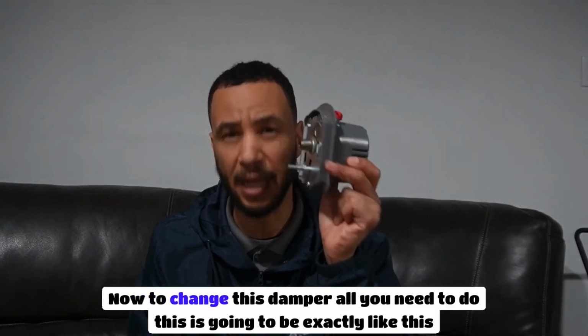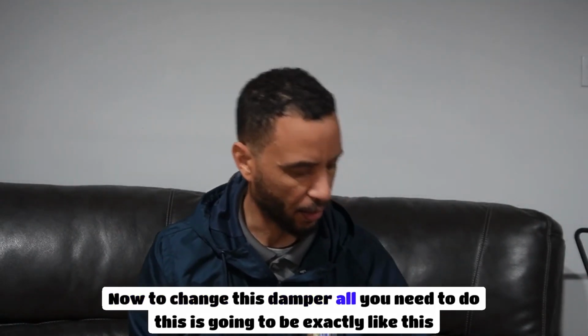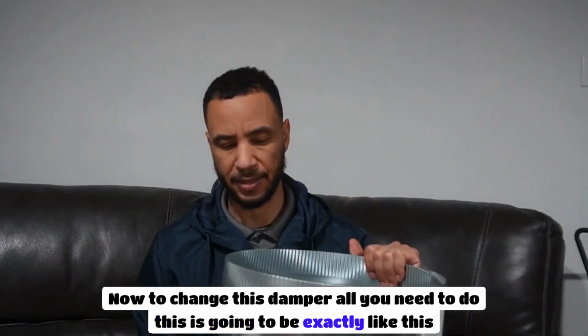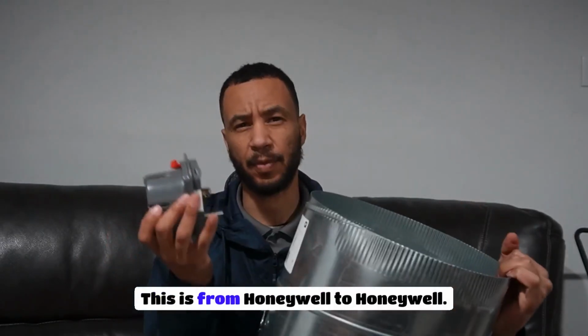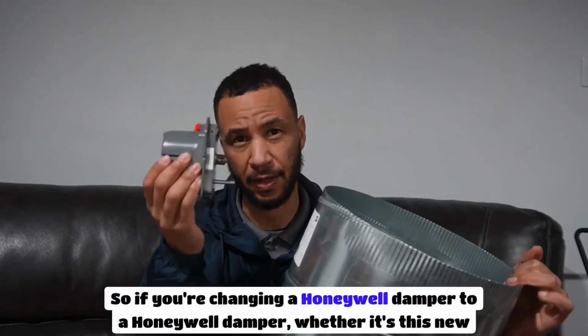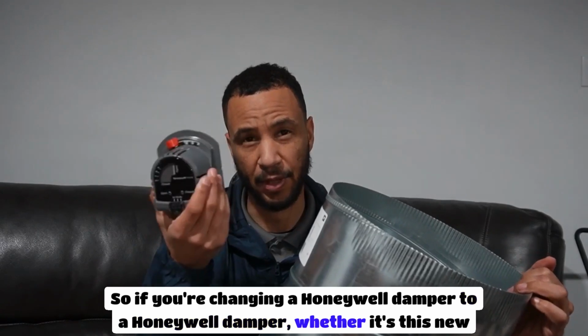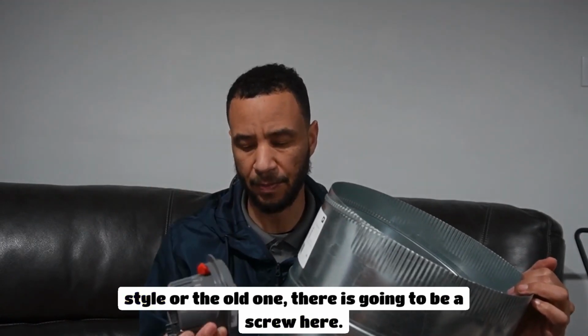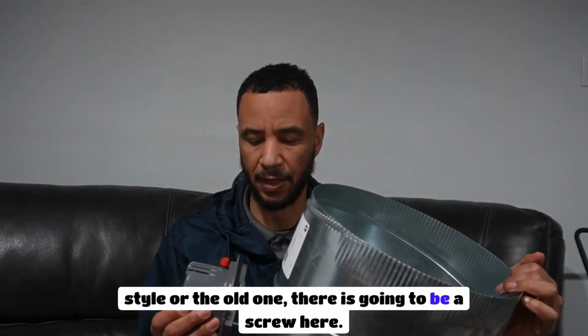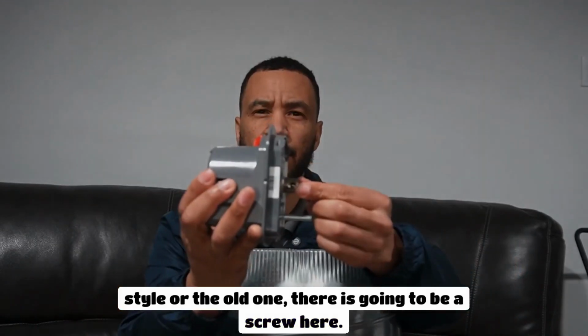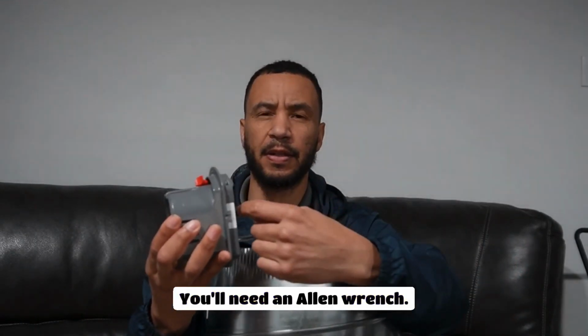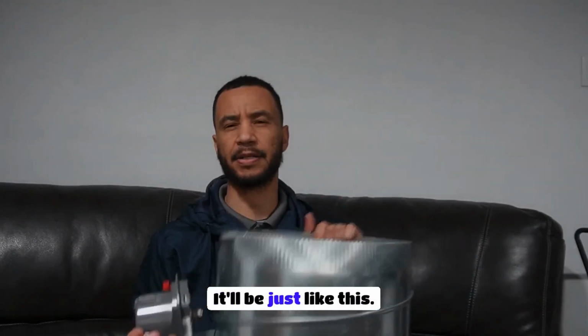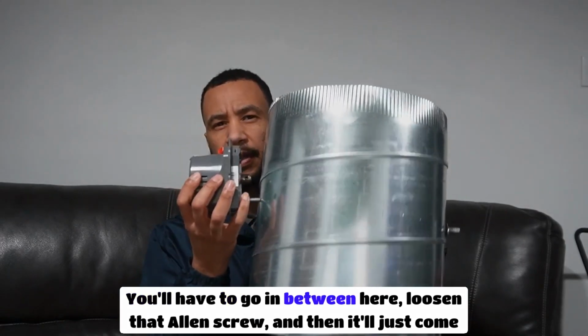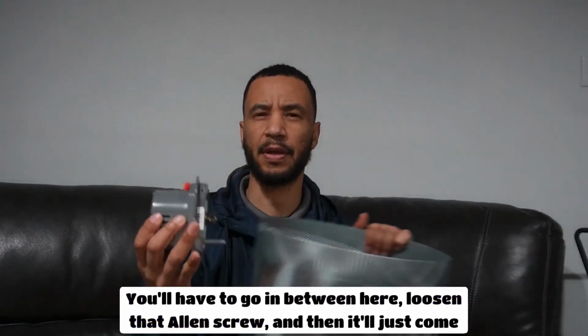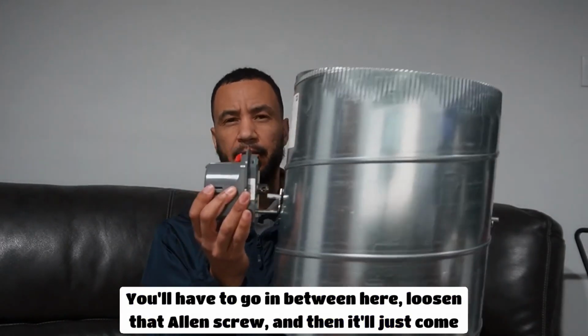Now, to change this damper, all you need to do, this is going to be exactly like this, all right? This is from Honeywell to Honeywell. So if you're changing a Honeywell damper to a Honeywell damper, whether it's this new style or the old one, there is going to be a screw here. You'll need an Allen wrench. You need to go in here. It'll be just like this. You'll have to go in between here, loosen that Allen screw, and then it'll just come straight out.